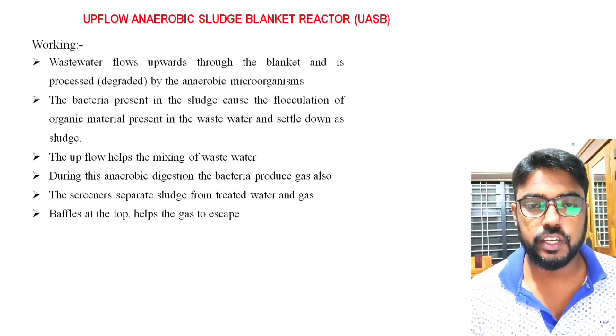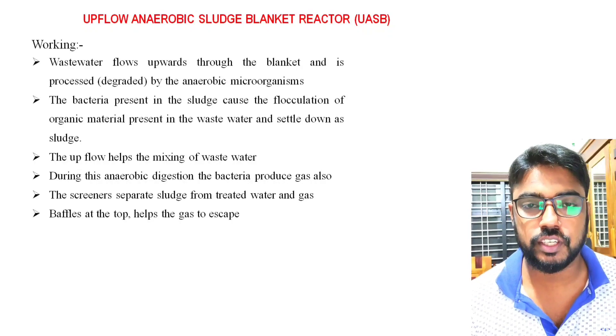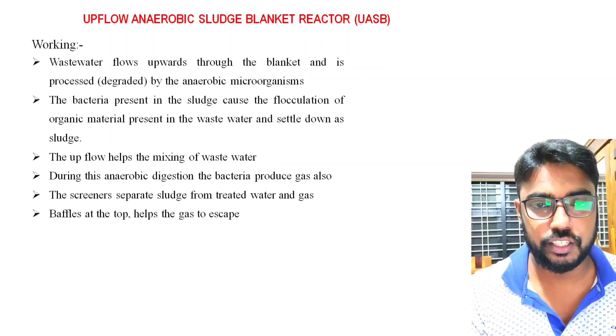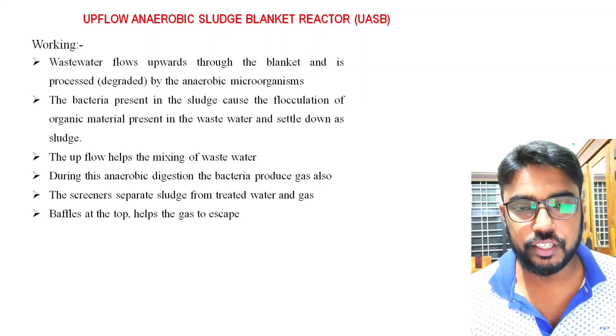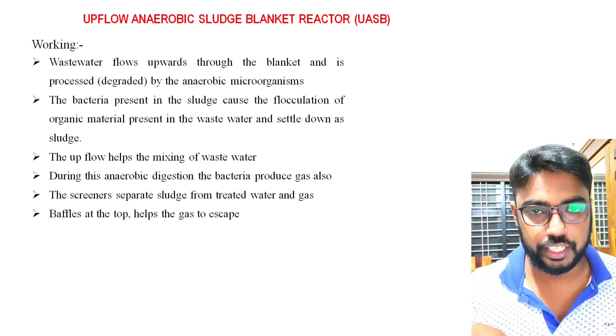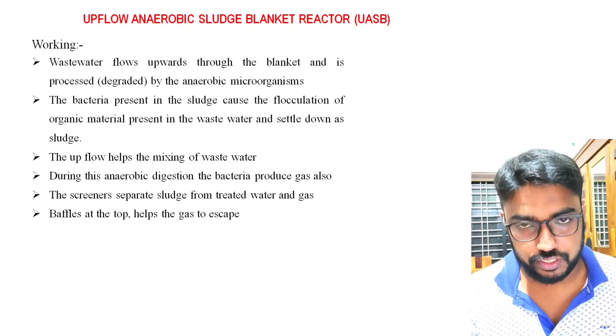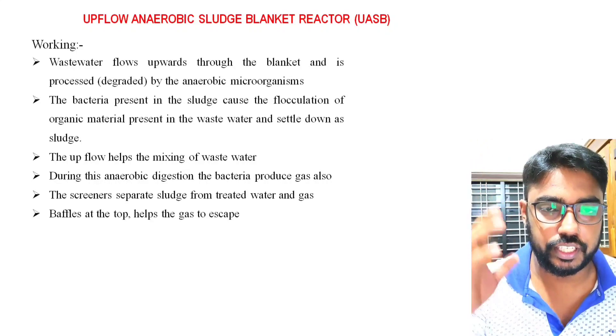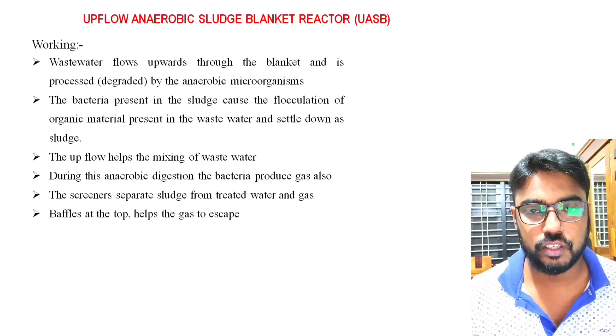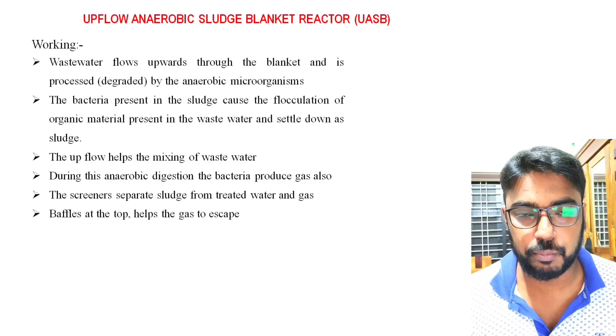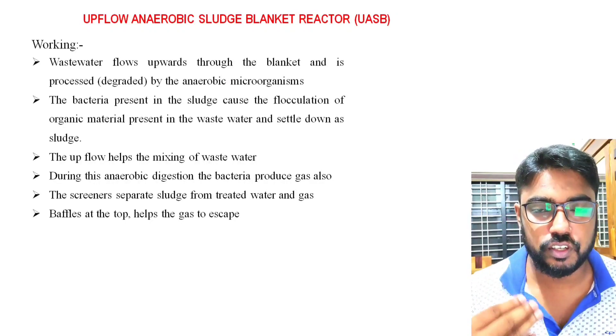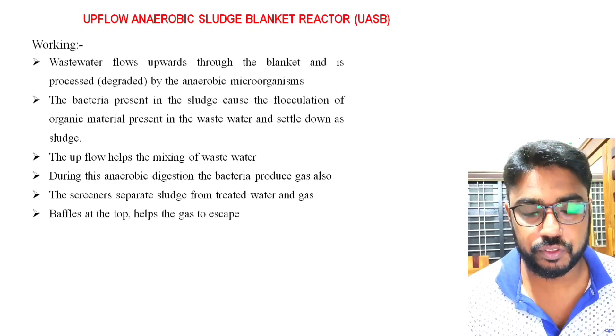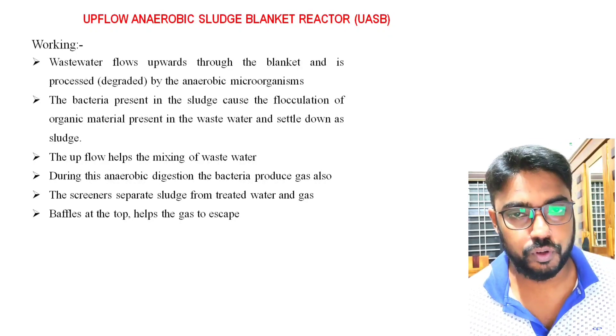Now we can see the working of the upflow anaerobic sludge blanket. The wastewater flows upward through the sludge blanket. The organisms present in the sludge degrade the organic materials, which then flocculate and settle as sludge in the lower sludge layer. The gas formed is removed from the top of the reactor. Screens separate the sludge from the treated water and gas. The gas escapes from the chamber via biogas outlets placed at the top of the reactor. The upward movement of wastewater also helps with mixing inside the reactor.